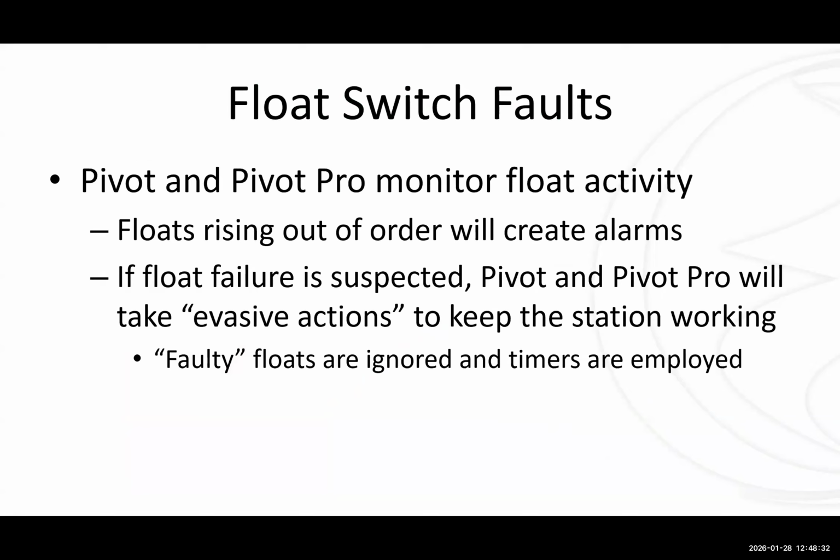This is probably one of the biggest scenarios that we run into. Float switch faults. Float switches in general, I would say, cause more problems in control panel applications than anything else. And we're not down on float switches. We like float switches. I'm not beating up on float switches.